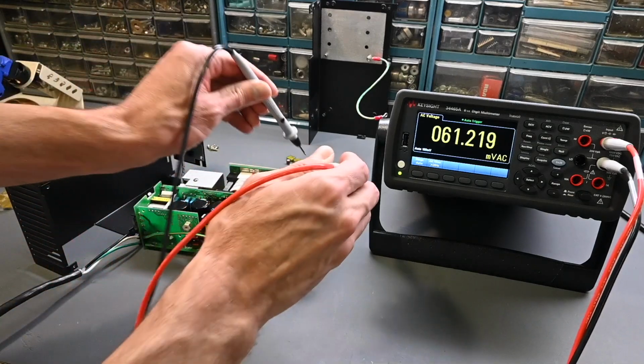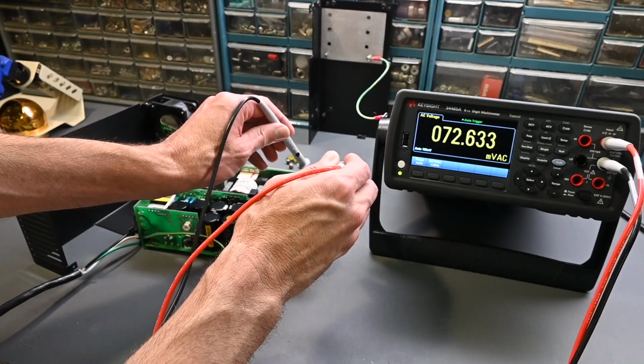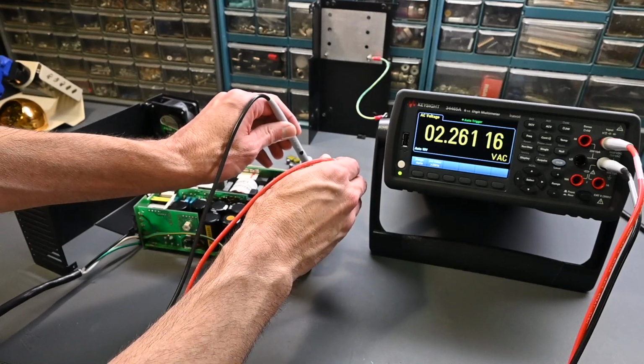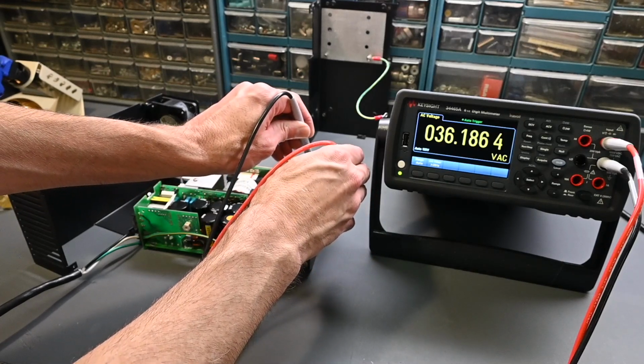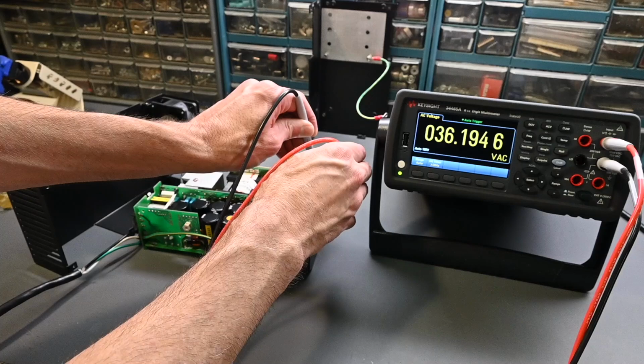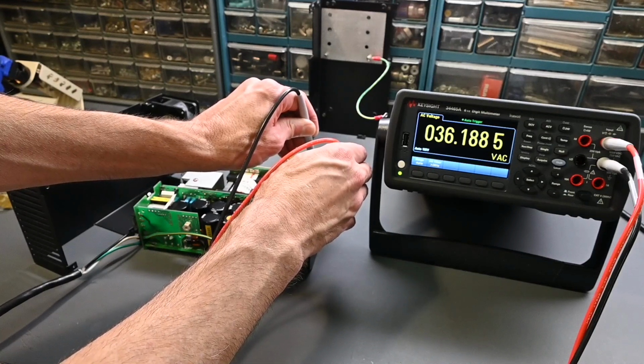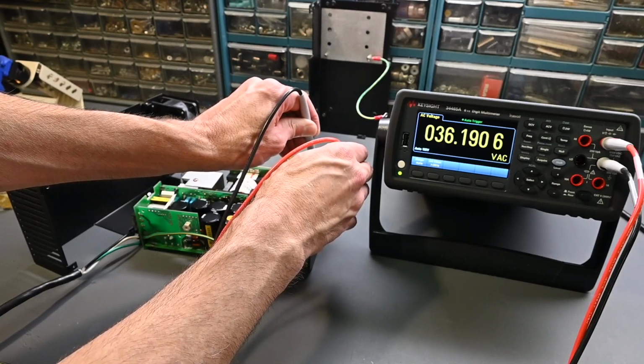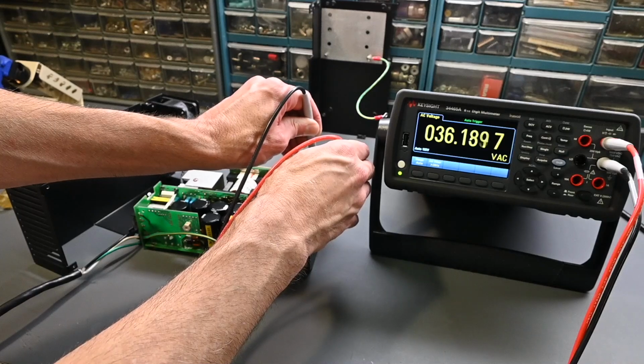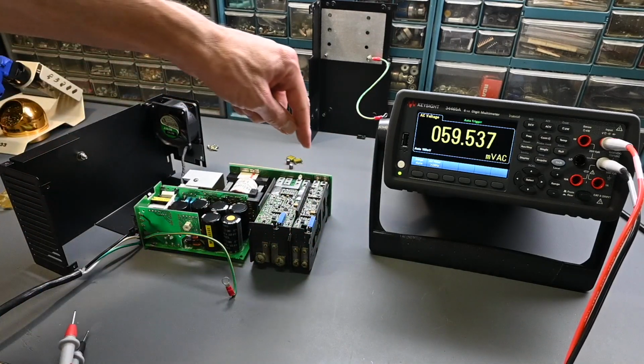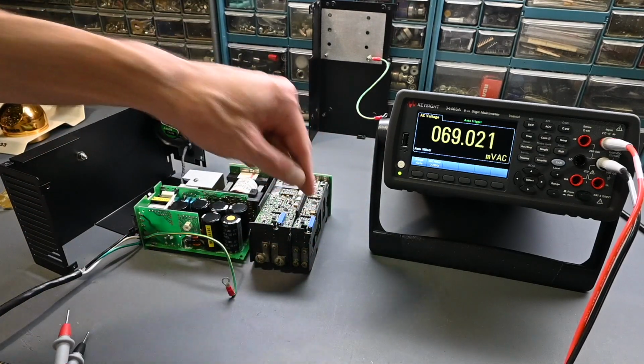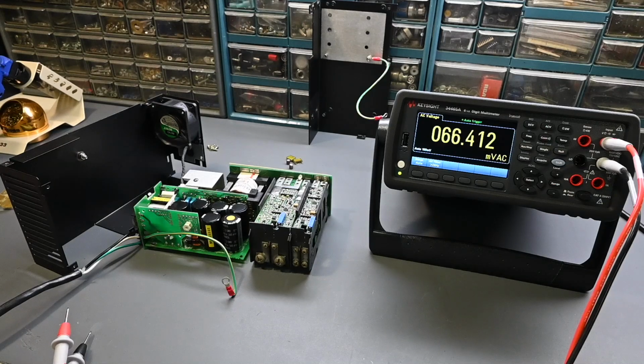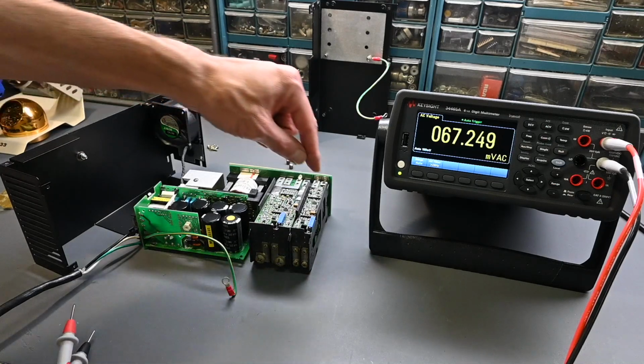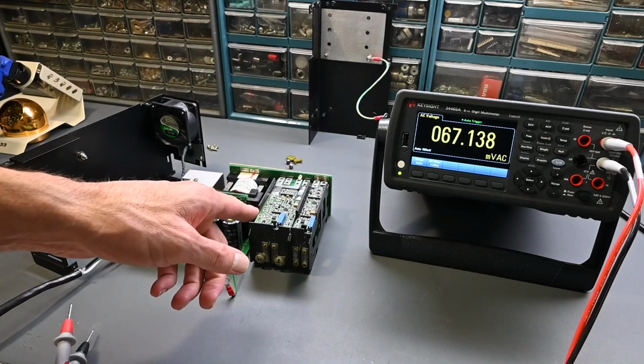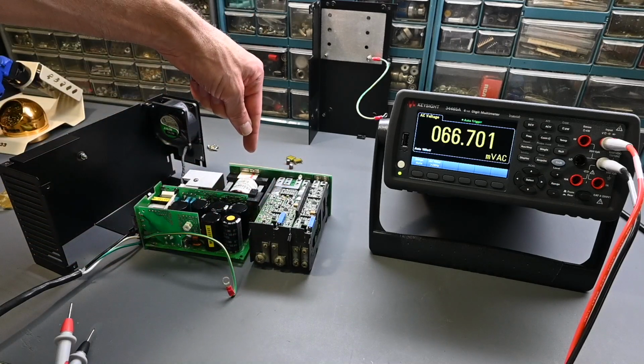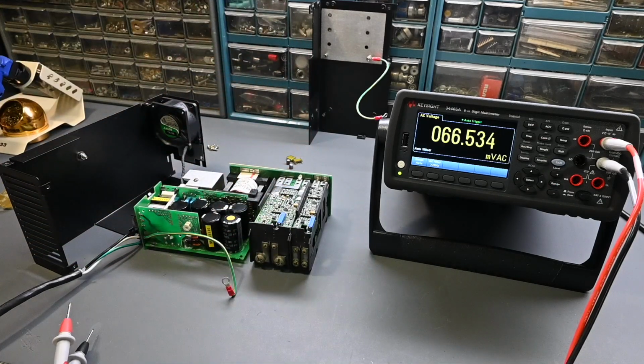So let's check the other module. 36 point, just shy of 36.2, 36.1918. And it makes sense that this is a lower voltage because this module only goes up to about 12 volts, maybe as high as 15 volts, but it is a lower output range than the other module, and this does have 2 secondary windings, so it makes sense that they're different voltages.